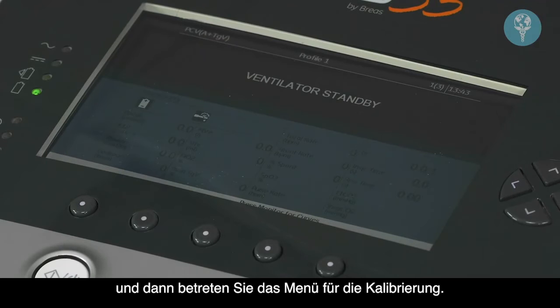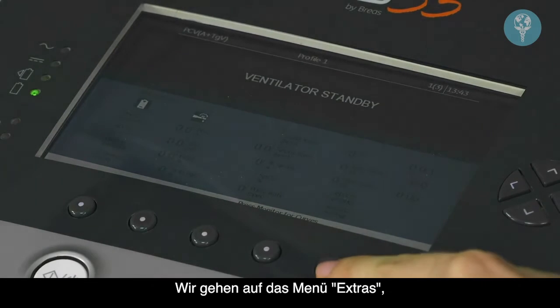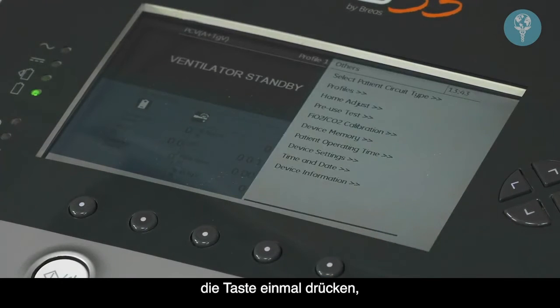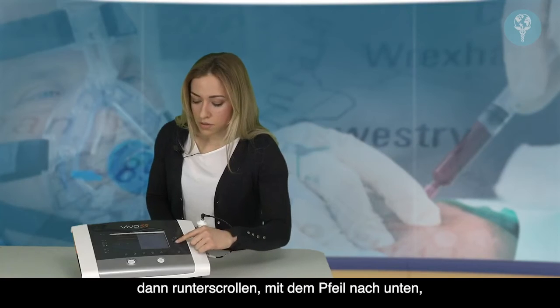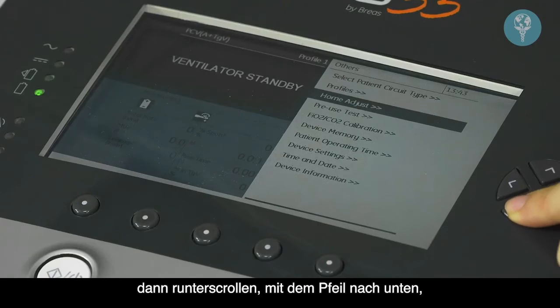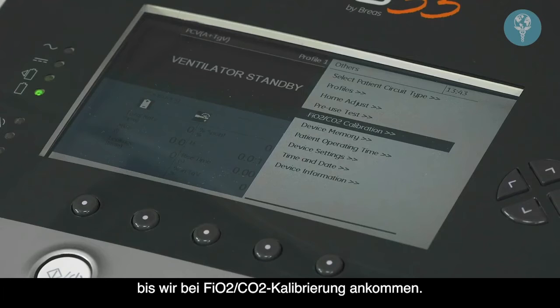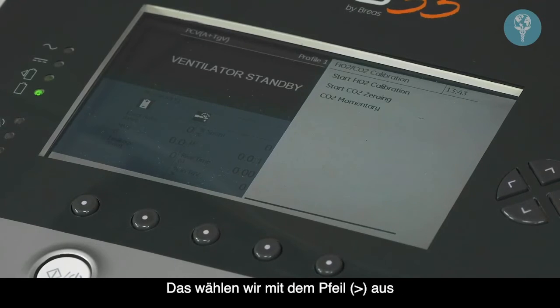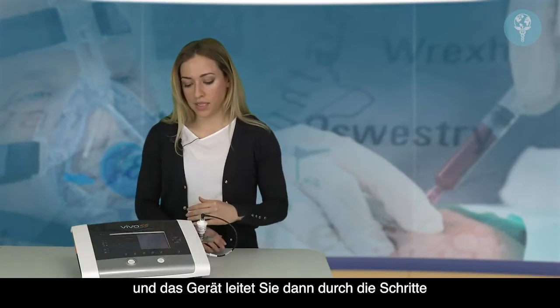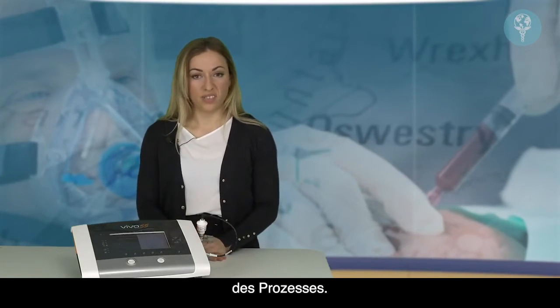And then to access the calibration in the menu, we want the Others menu. Push that button once. We can then scroll down with the down arrows until we get to FiO2/CO2 calibration. Then we want to push the arrow to select that, and the device will then take you through the step-by-step process of how to do that.